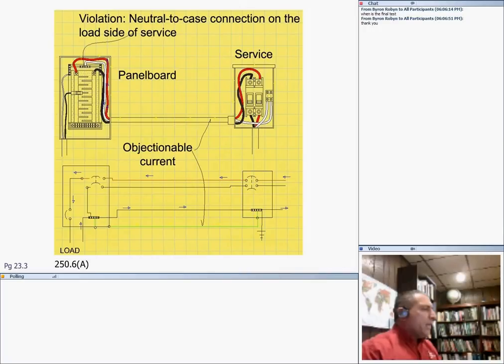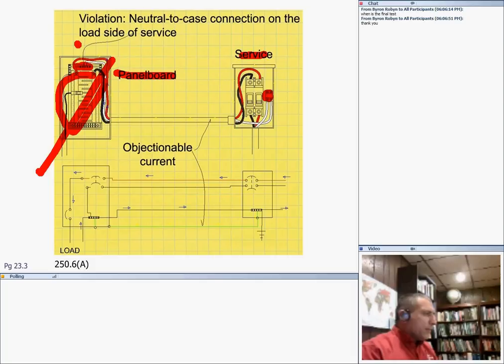So, the case connection on the load side of the service, as we just talked about: in a service, if this is a panel, you need to tie the neutral and the ground together at the service, you don't do it in the panel. This is a violation. You have to do this only. The neutral and the ground are bonded together only at the service. So can you see that, where we only bond right in here, and we go to Mother Earth right at the service. You bond again here. You don't bond again here.